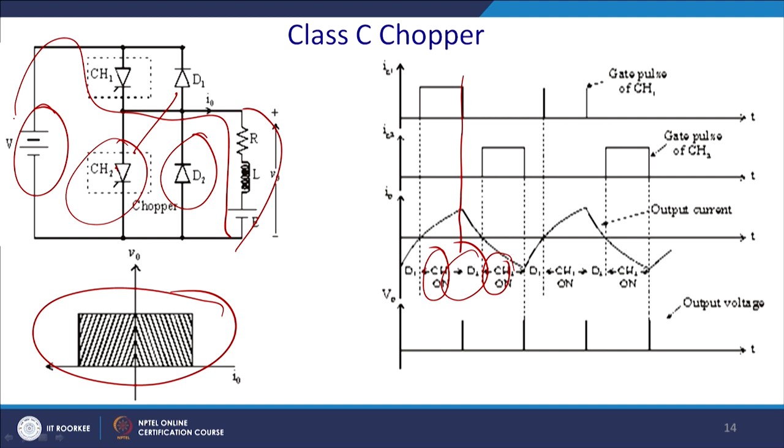Most of the cases, we generate this voltage by rectification, by the diode rectifier, and thus it is unidirectional; current can flow from the AC side to the DC side. Unless you use a fully controlled converter or an active rectifier, power is not possible to feed back to the source. So, then what will happen if there is a capacitor? This voltage will swell up. So, this is one of the issues while operating in the regenerative braking mode. For this reason, we may add a braking resistor here if we want protection of this circuit.